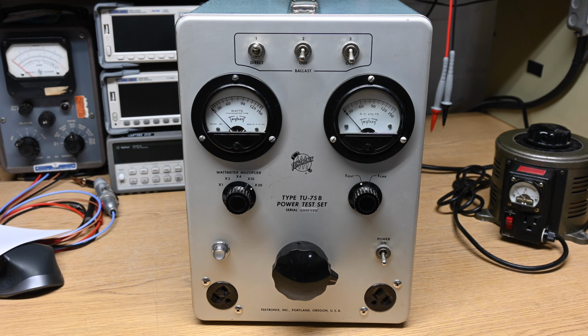Here's a closer look at the front of the device. First, you've got your main power switch here in the bottom right. You've got the knob for your variac, and that variac goes from 0 to 140 volts. There's your power lamp showing that it's on. Down here, both of these outlets are actually the same. They're wired together internally, so they both are affected by the variac and the bulbs. It's not like one of them is just straight line voltage or anything like that.